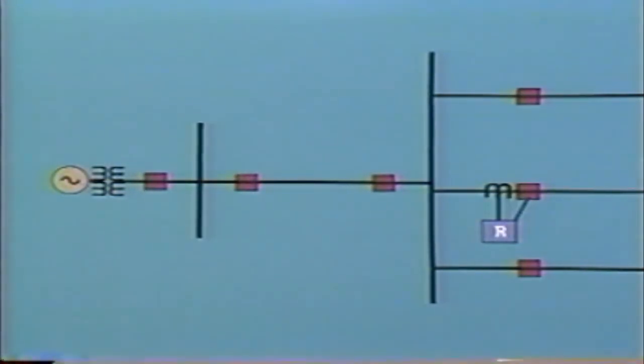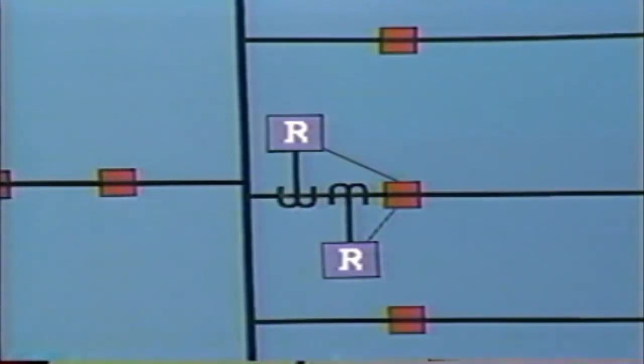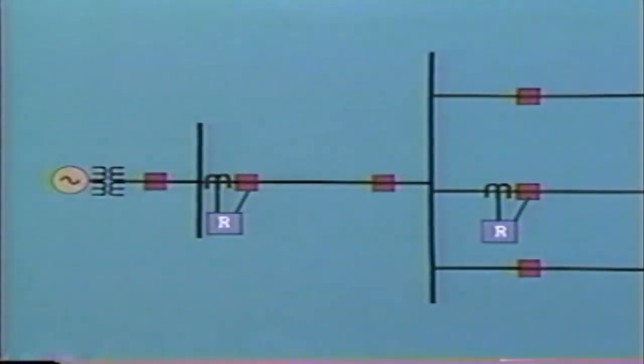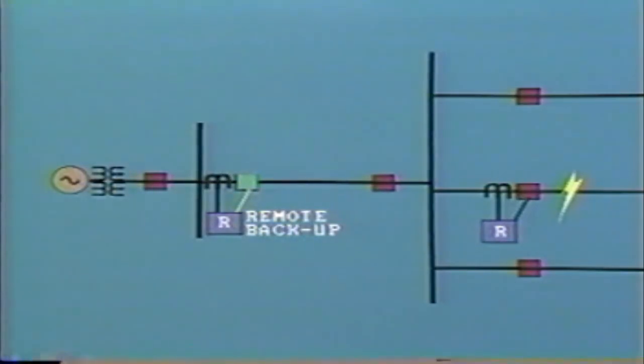For this reason, it is customary to install additional or duplicate relays to provide backup. If the backup relays are installed in the same station as the primary relays, this is known as local backup. Sometimes backup relays are located at a remote station, and this is called, logically, remote backup. Here we see the fault way out along the line, but the local protection fails to operate. The remote backup will then operate to open this breaker and so clear all of this line, as well as the bus and other outgoing feeders.